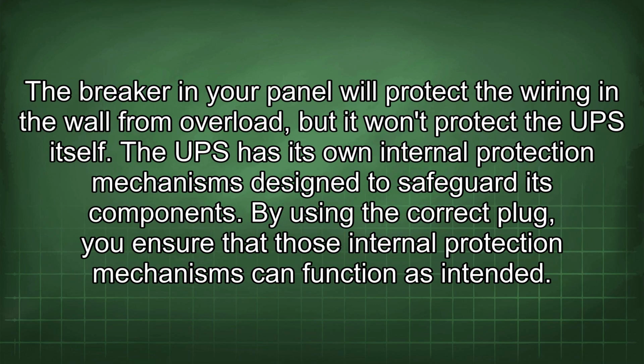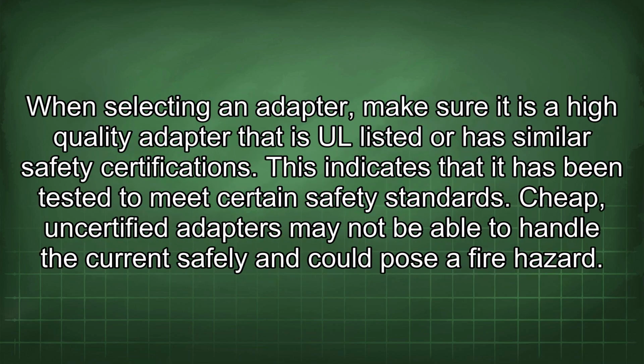The breaker in your panel will protect the wiring in the wall from overload, but it won't protect the UPS itself. The UPS has its own internal protection mechanisms designed to safeguard its components. By using the correct plug, you ensure that those internal protection mechanisms can function as intended. When selecting an adapter, make sure it is a high-quality adapter that is UL listed or has similar safety certifications. This indicates that it has been tested to meet certain safety standards. Cheap, uncertified adapters may not be able to handle the current safely and could pose a fire hazard.